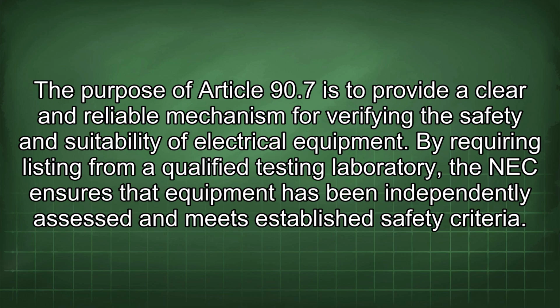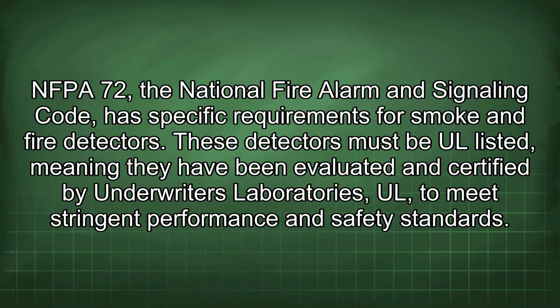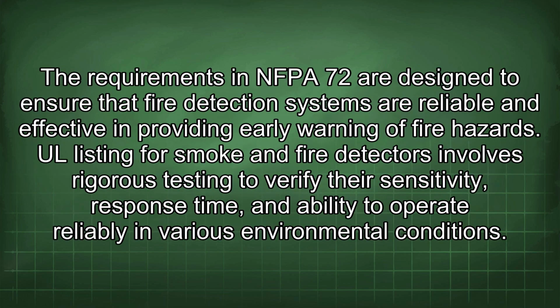NFPA 72, the National Fire Alarm and Signaling Code, has specific requirements for smoke and fire detectors. These detectors must be UL listed, meaning they have been evaluated and certified by Underwriters Laboratories, UL, to meet stringent performance and safety standards. The requirements in NFPA 72 are designed to ensure that fire detection systems are reliable and effective in providing early warning of fire hazards. UL listing for smoke and fire detectors involves rigorous testing to verify their sensitivity, response time, and ability to operate reliably in various environmental conditions.